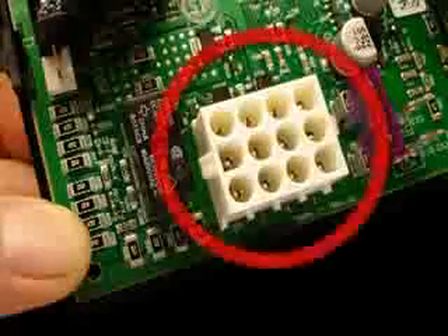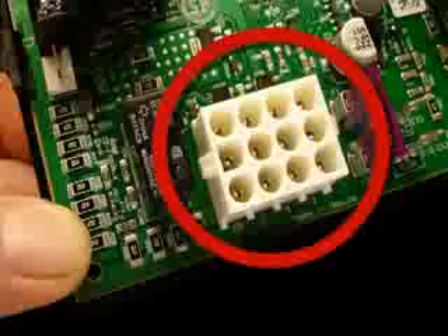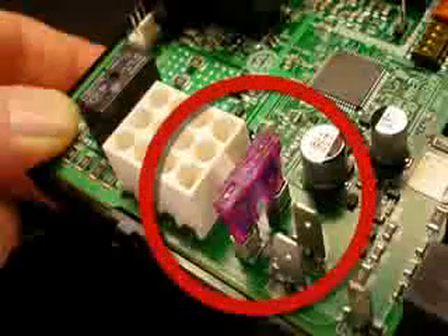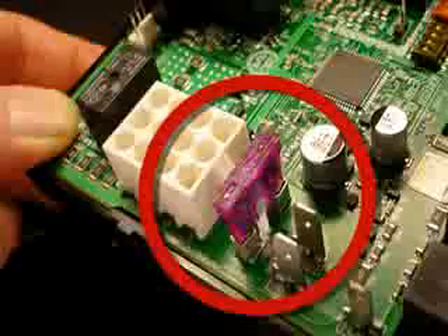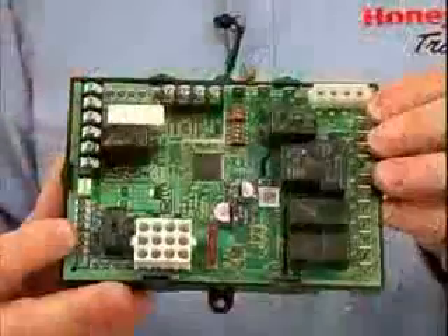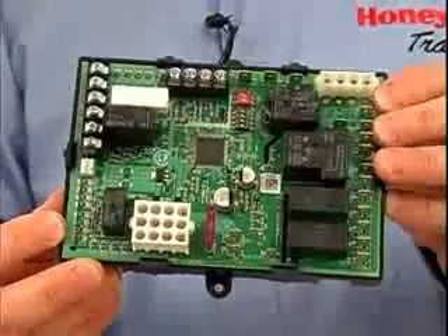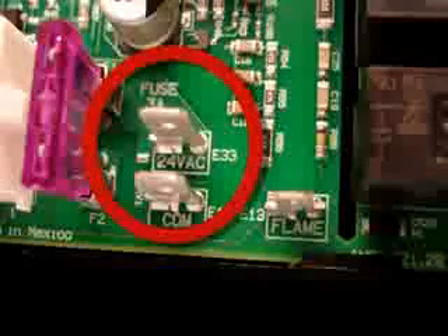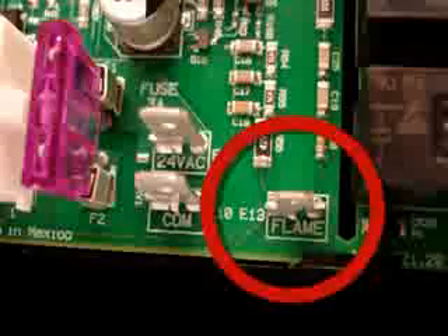Here is the main harness plug that connects all the low voltage circuits, such as limits and gas valves. It also contains an optional flame sensor connection to detect flame. This fuse protects the board against shorts in any of the low voltage circuits. The 24-volt control circuit transformer output connects to the board here, and this is another connection option for the flame sensor on the burner.